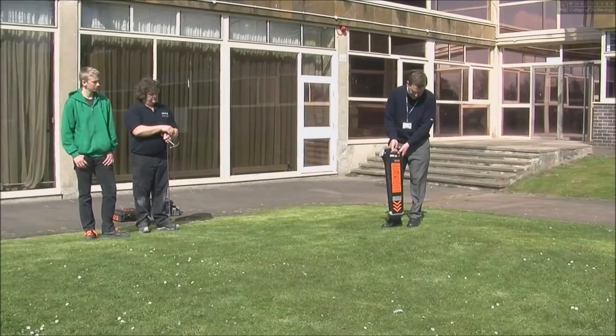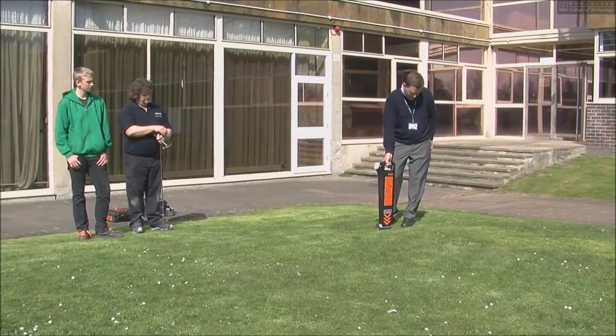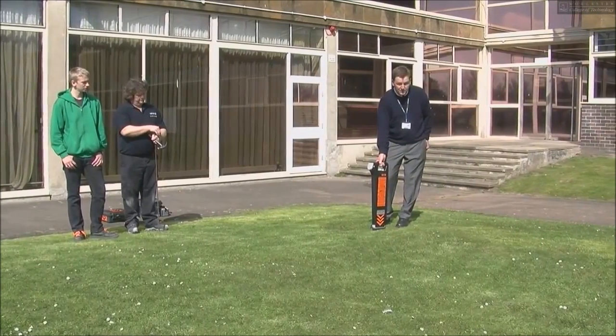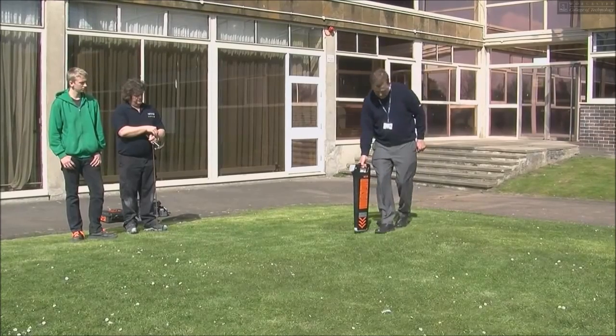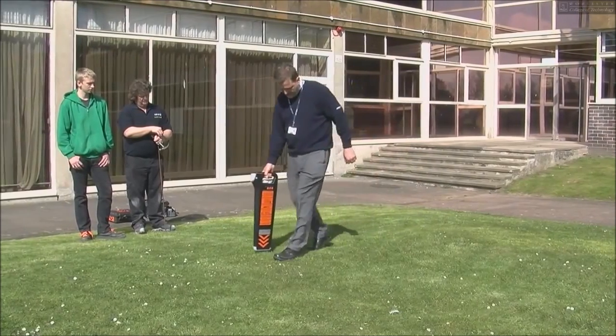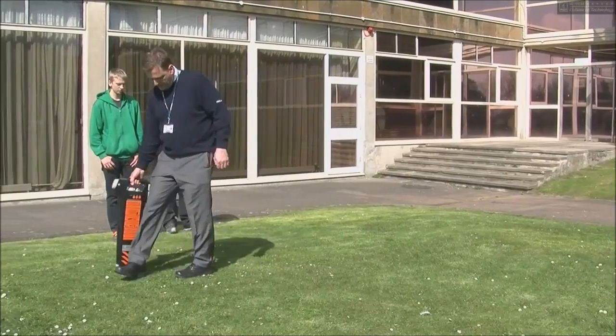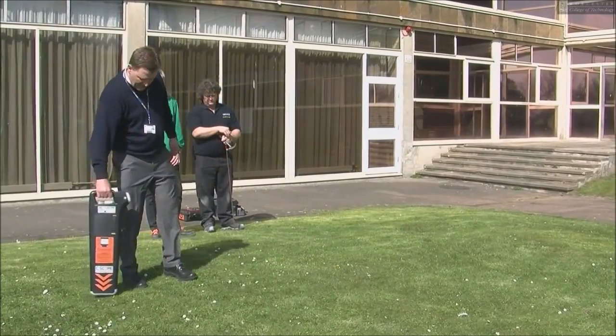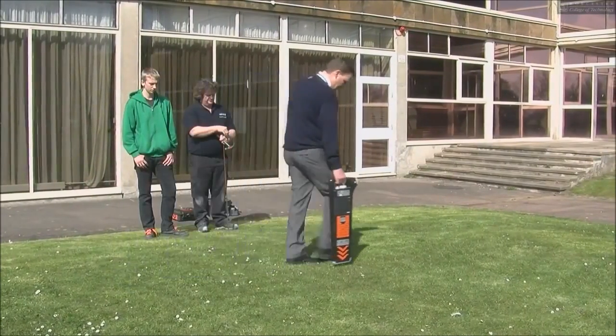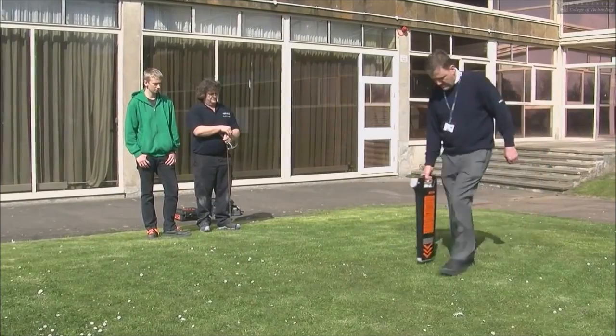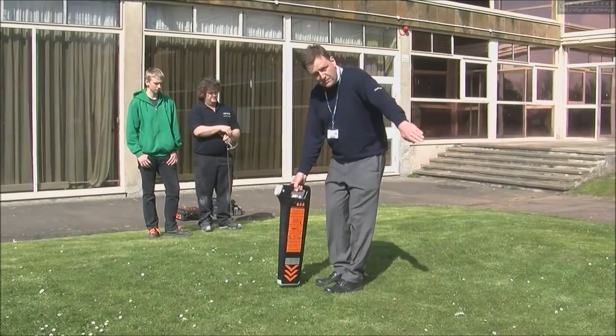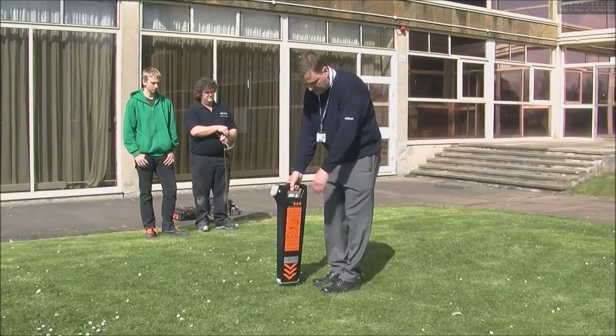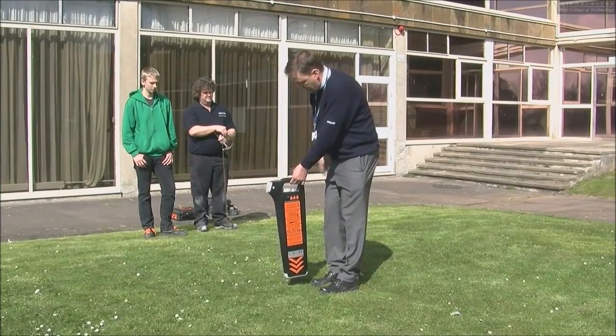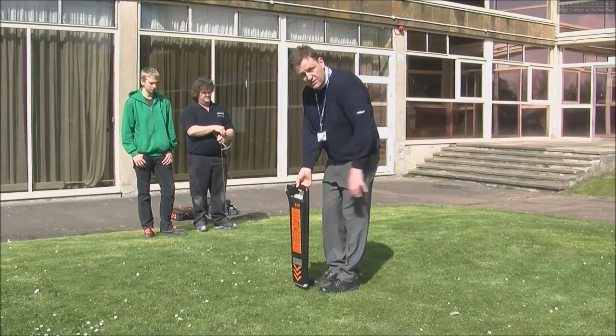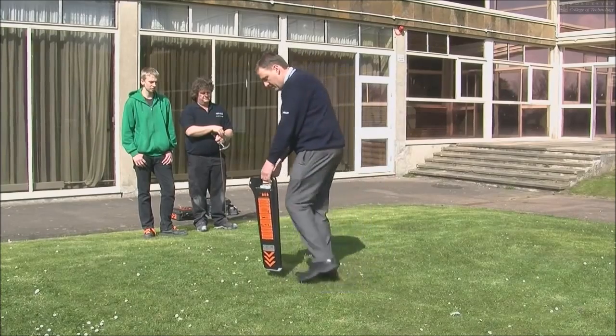First, to actuate the cable avoidance tool is by moving my hand onto the trigger. This makes a beep. I then hold the detector approximately an inch from the ground, and I move in a straight line across the area that I need to check, moving backwards and forwards. This is actually detecting any cables that are running in this direction. To actually see if there's any cables running in that direction, I need to move the detector 90 degrees and do the same process.